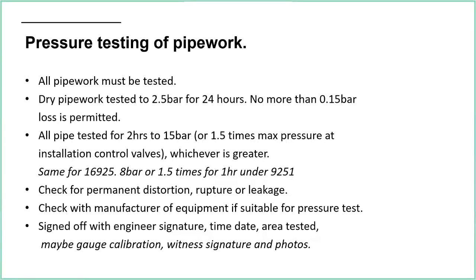But as I say, manufacturers should be on the ball because they should know that test needs to be carried out anyway. So all of this should be signed off with the engineer: an engineer's signature, a time and date, the area tested. Again, you're probably not going to be hydrostatically testing all of the system in one go. You're probably going to be testing each zone as a whole, or just the riser. And then you need some information about which bit you've tested.